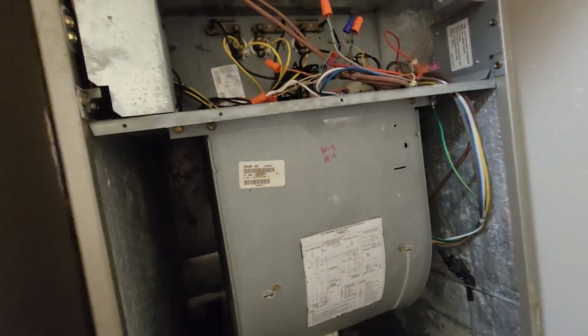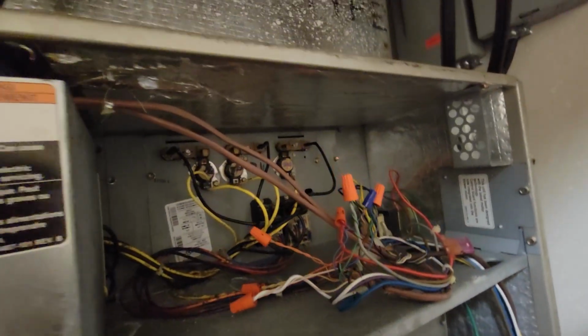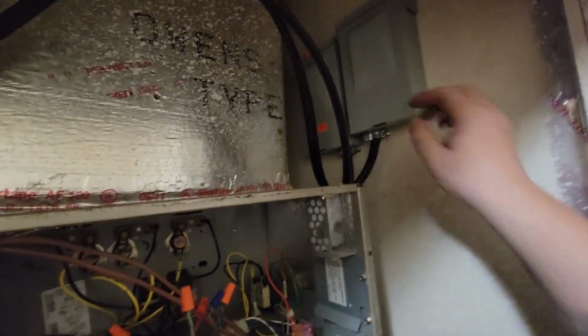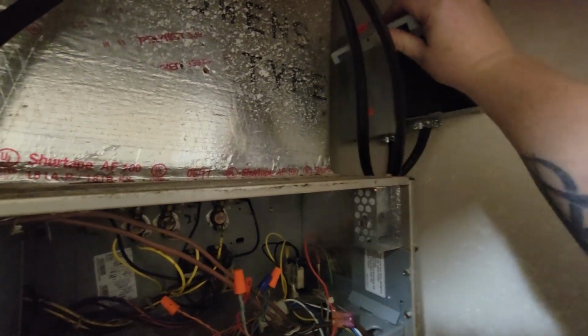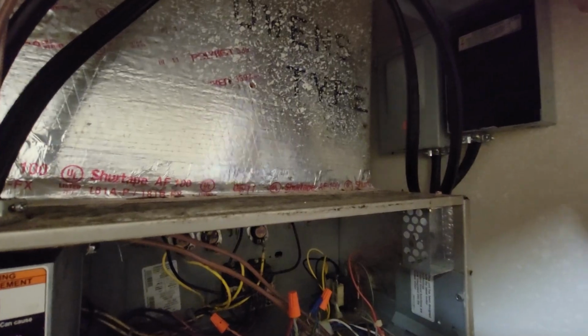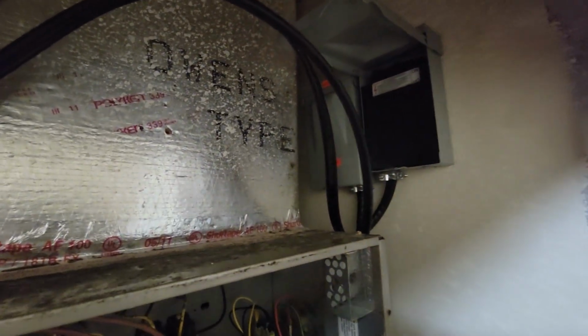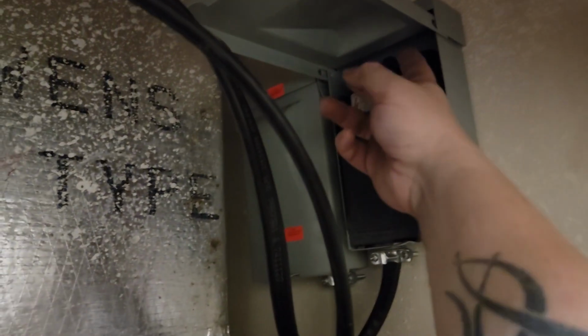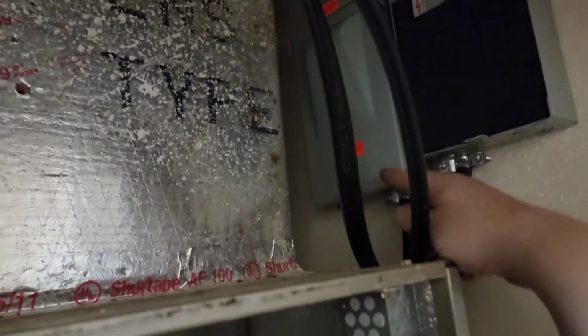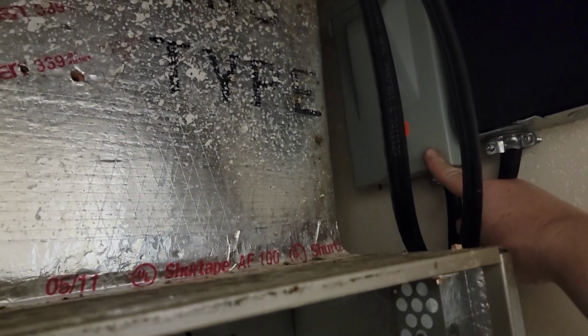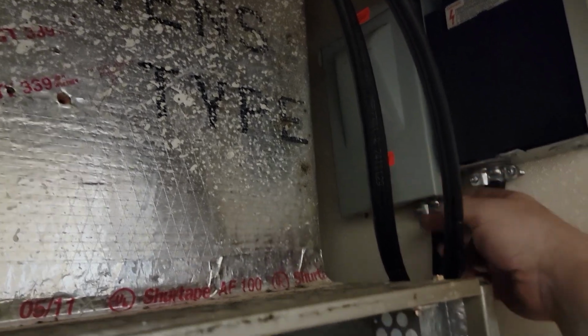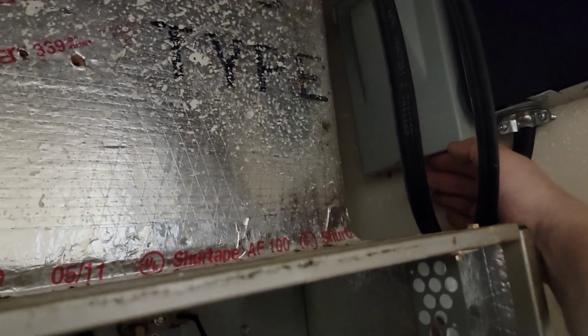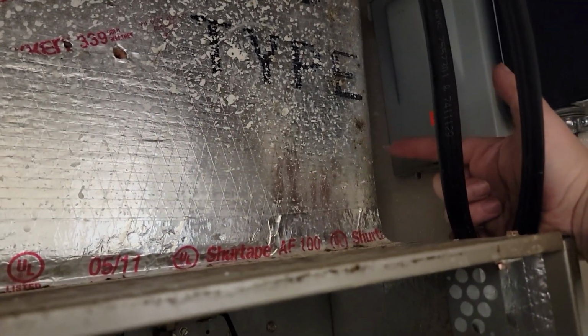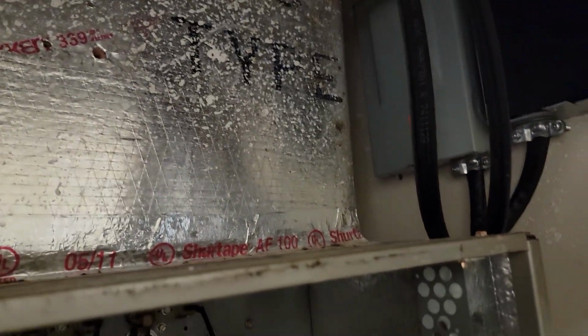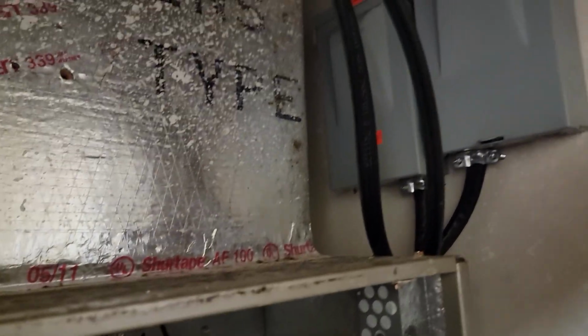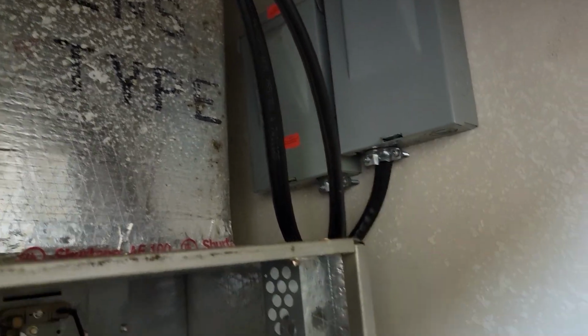Now, there are some things we'll typically check as well. Depending on your setup, you might have a little box over here that lifts up, with a little disconnect - let me zoom in a bit - a little device you pull out to disconnect from power. I've got a second one that allows me to remove AC. However, whoever did this install wasn't really thinking it through, so this lid contacts our ducting over here, and I can't lift it up enough to pull out the device.